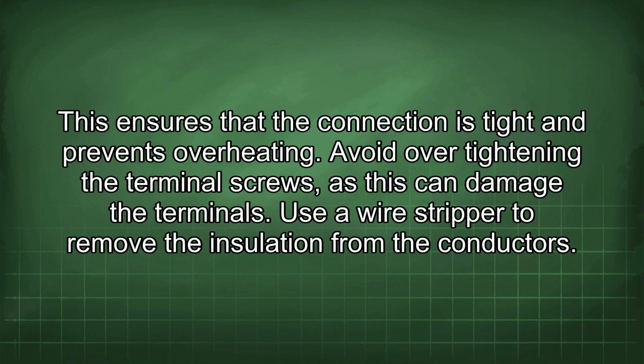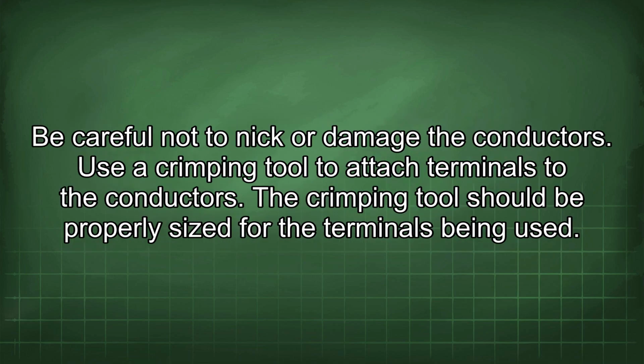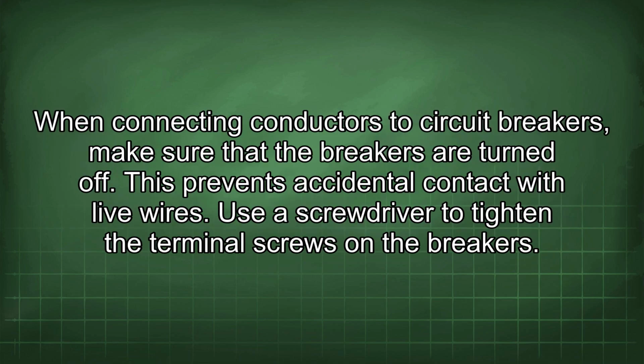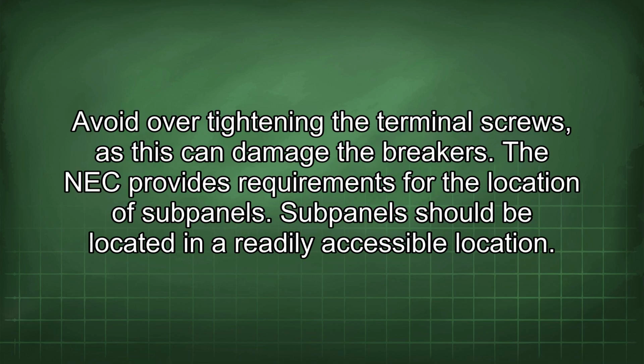Use a wire stripper to remove the insulation from the conductors. Be careful not to nick or damage the conductors. Use a crimping tool to attach terminals to the conductors. The crimping tool should be properly sized for the terminals being used. When connecting conductors to circuit breakers, make sure that the breakers are turned off. This prevents accidental contact with live wires. Use a screwdriver to tighten the terminal screws on the breakers. Avoid over-tightening the terminal screws, as this can damage the breakers.